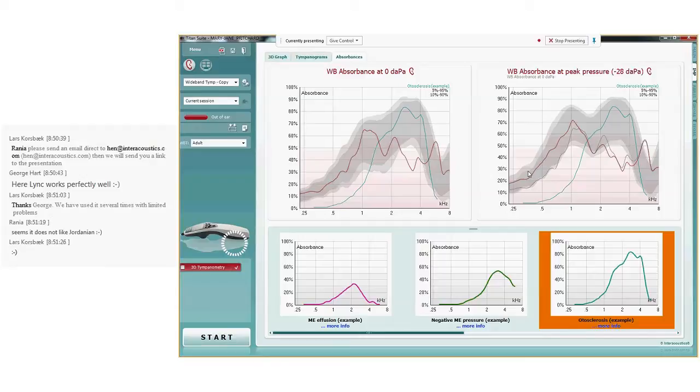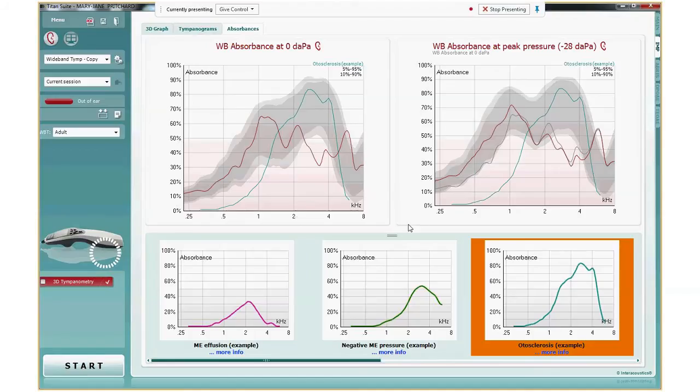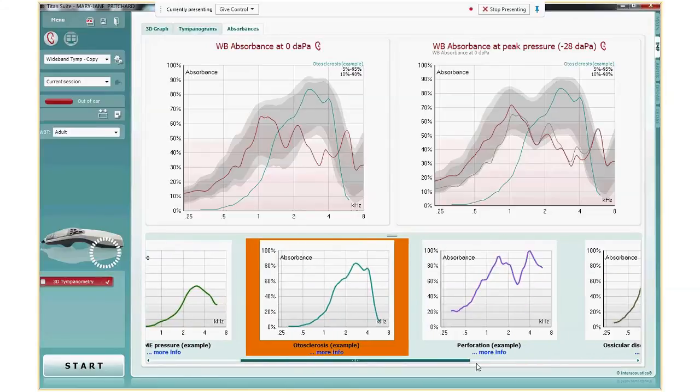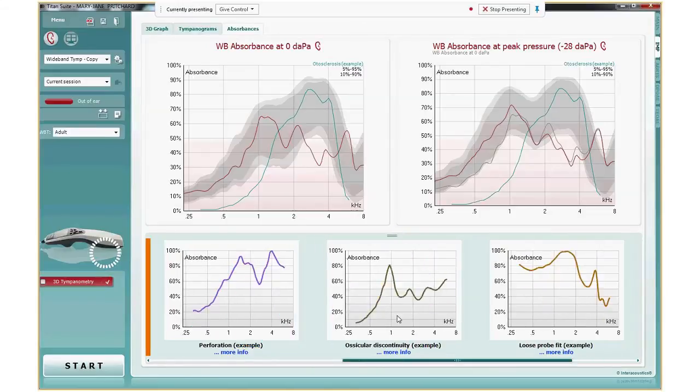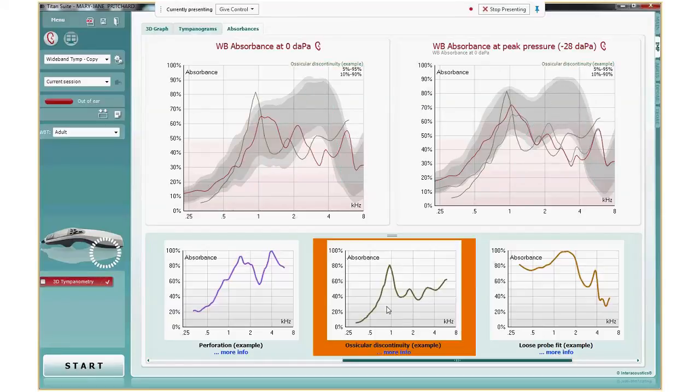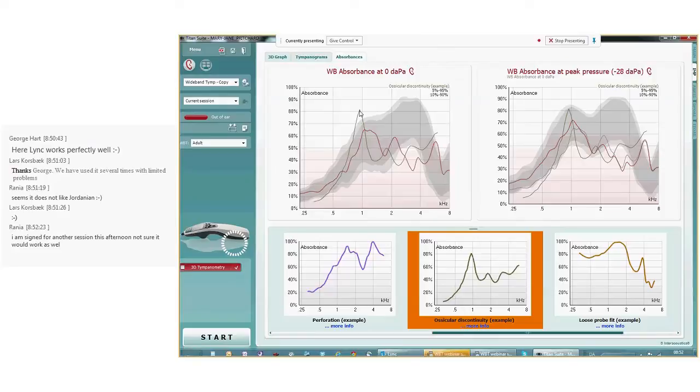Now, the problem is that we were not allowed to put such normative data for pathologies in our system, because the research so far available is not having big enough populations for us to be allowed to implement it. Let me show one example more, because I think the ossicular discontinuity is very interesting. The ossicular discontinuity is an example where there is a high peak of absorbance. This high peak is typically close to the resonance frequency, and very often this peak is even at a lower frequency than in the example that we show here.